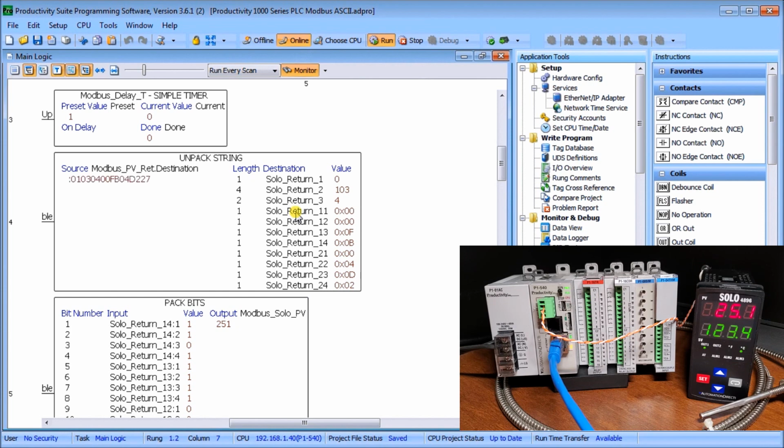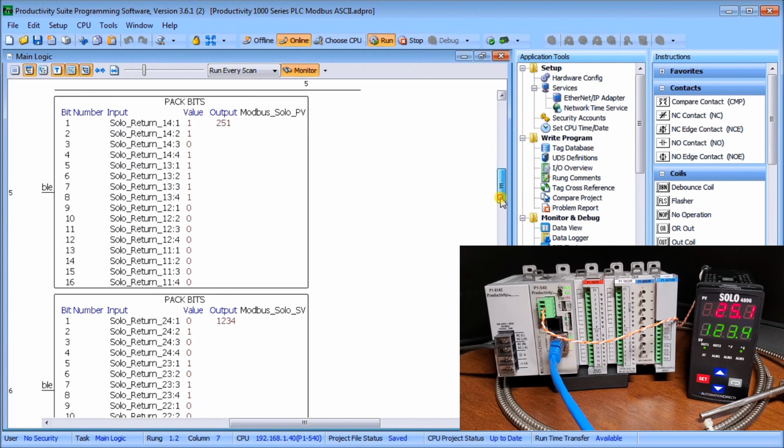First of all, let's take the raw hex value. We'll take 1 8-digit, and each one of these represents 8-bit unsigned. So 00FB is the first number we want, and 04D2 is the second number. Once we have those bits in, we can pack them into a normal register. As we pack them in, we sort them out from our return, and we come up with the value of 251, now a decimal number.